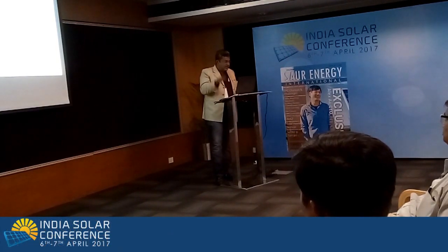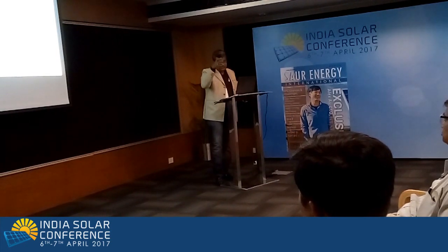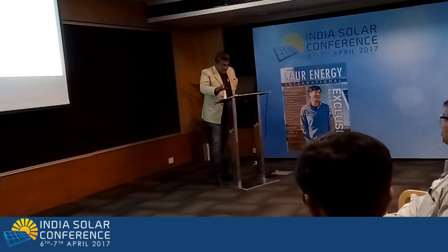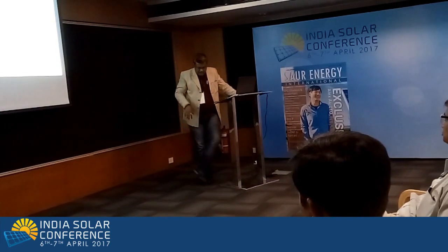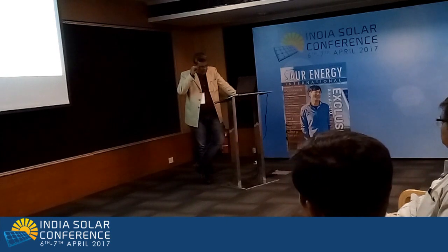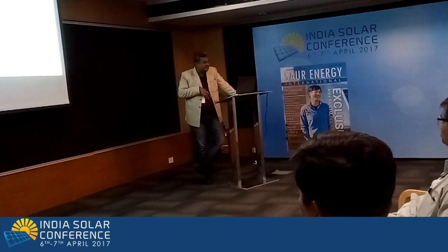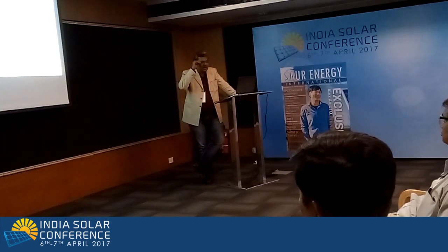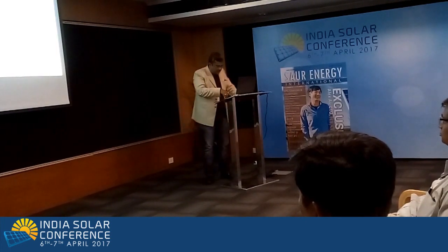Forecast error is a good thing to measure the accuracy of anyone's forecast. One thing is that if you see any other documents, the forecast accuracy is stated using root mean square error or mean absolute error, etc. In the case of Indian regulation, it is totally changed. They say it is a point regulation. That is, at each and every time block they will calculate the accuracy, and at that time block, if it is not within plus minus 15% or plus minus 10%, they will put some penalty on you.